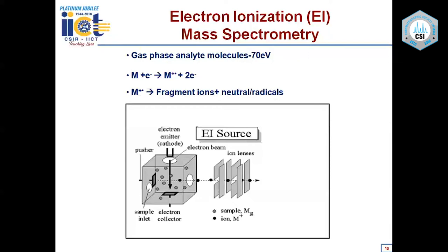Fragmentation occurs because of excess energy — for example, an excess energy of 30 eV equals about 3,000 kJ/mol, while bond energies of most chemical bonds (C–H, C–X, C–O) lie in the range of 300 to 600 kJ/mol. This excess energy drives fragmentation, producing many fragment ions that help in structural elucidation. The ions formed in the source are repelled by the repeller into the analyzer, given acceleration voltage, and the ion beam is focused by ion optical lenses.